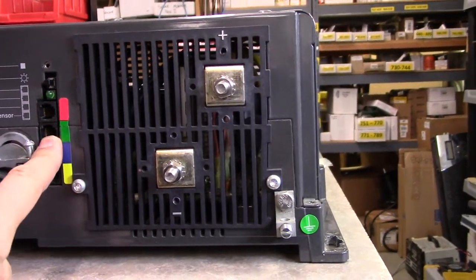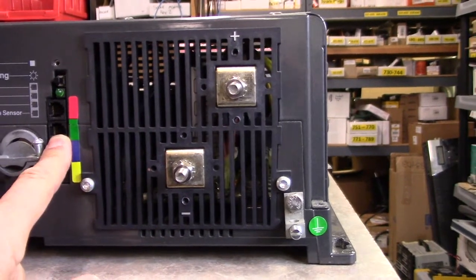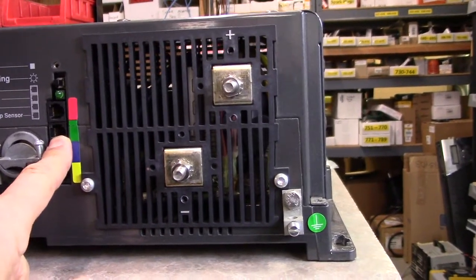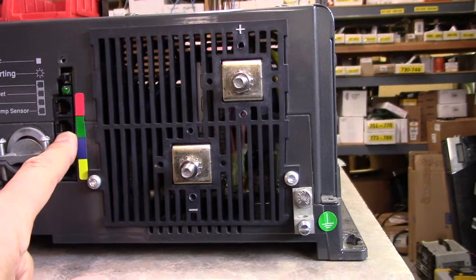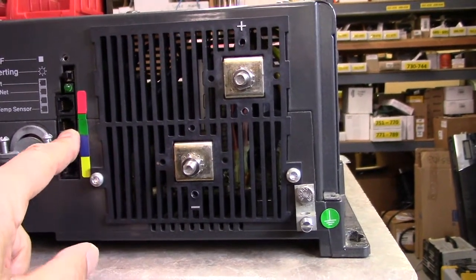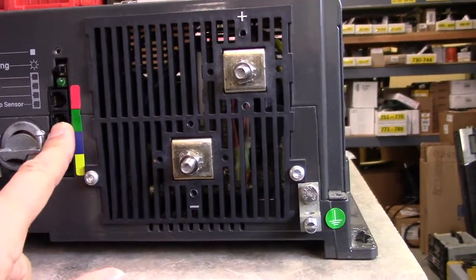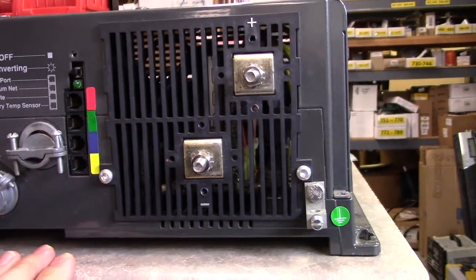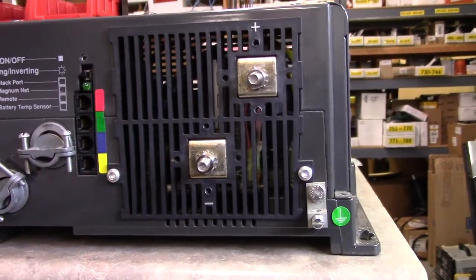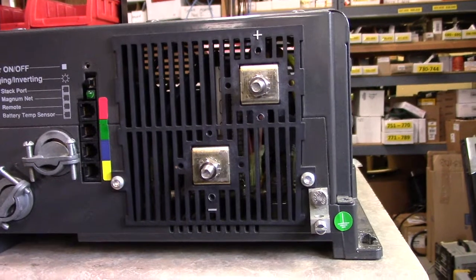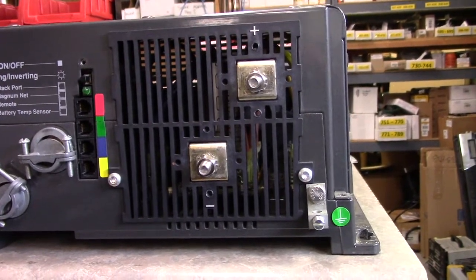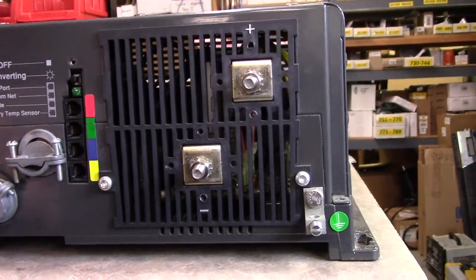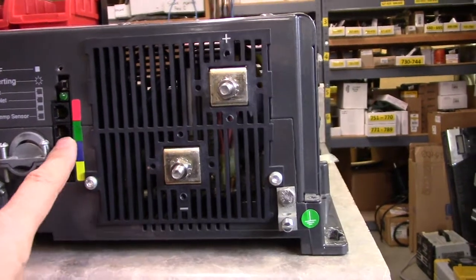The green port, if you see a cable in here, is most likely going to an automatic generator starting system. It's like a network communication port, and it will plug into another control box that can start and stop your generator based on if your battery is getting low, and other features as well.